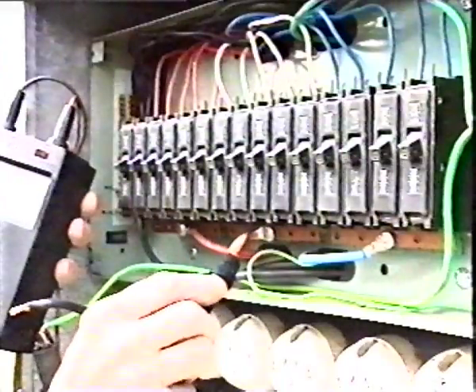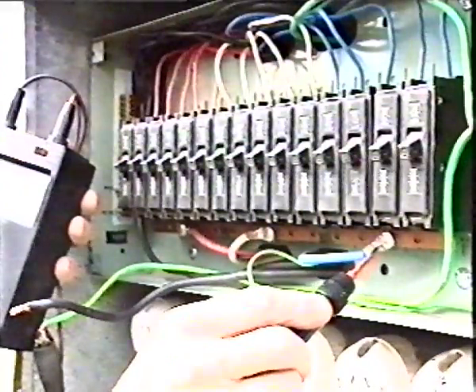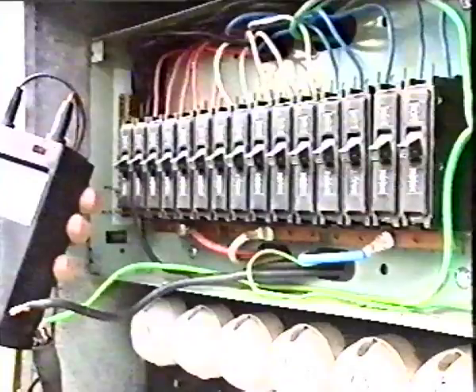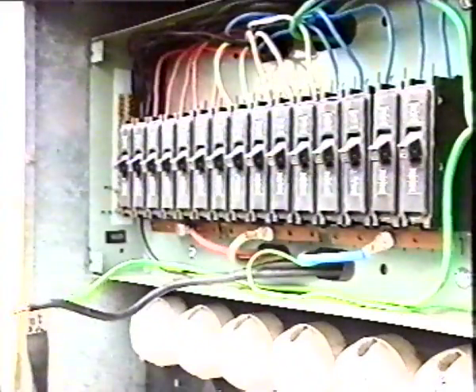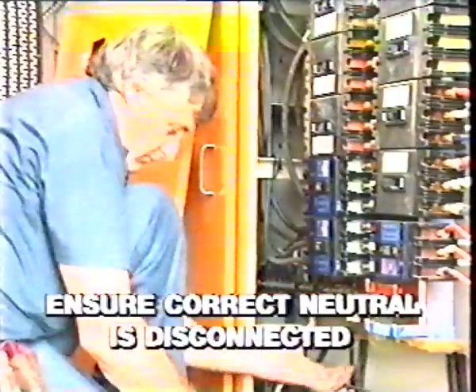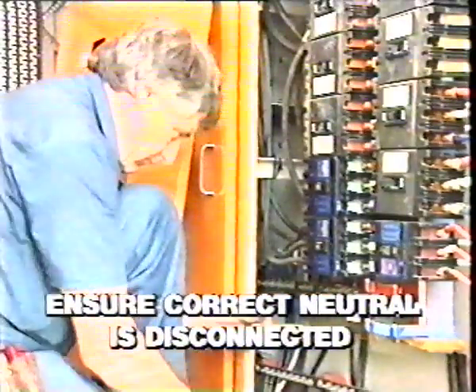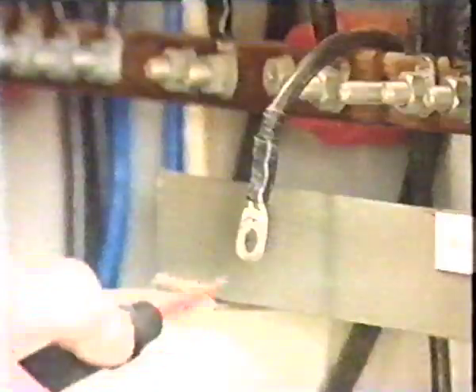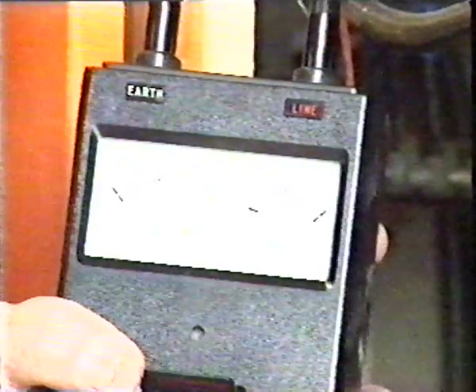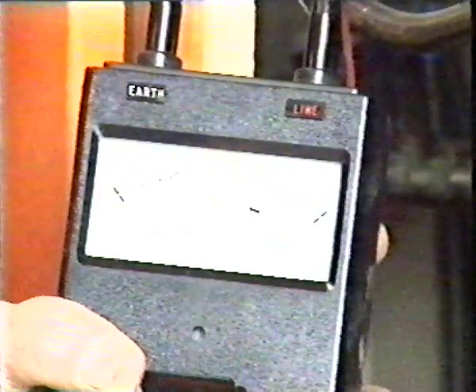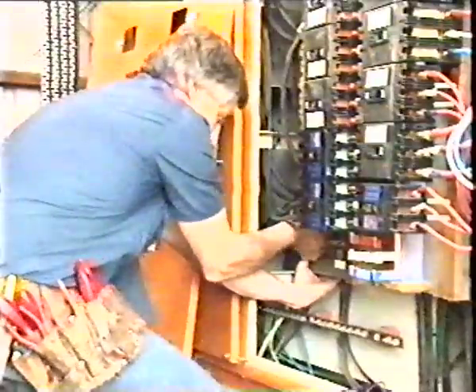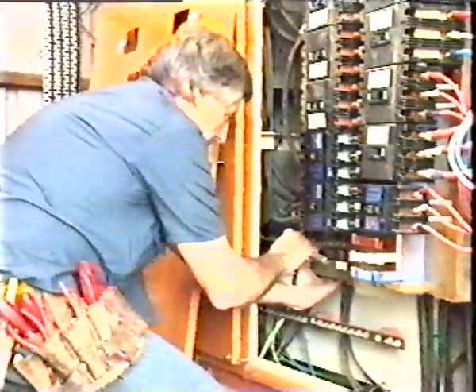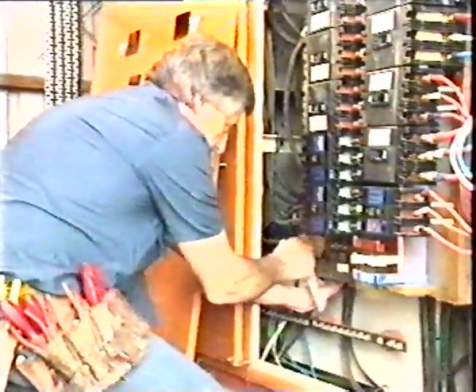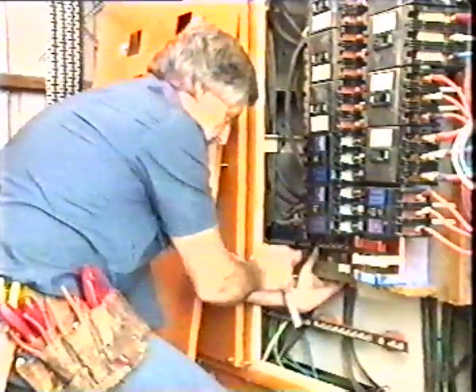Test the insulation resistance of the sub-main active conductors. A high resistance will establish that the conductor is not connected to earth and is therefore not a neutral conductor. Disconnect the sub-main neutral conductor from the supply switchboard neutral link. Test the insulation resistance of the conductor. Reconnect the sub-main neutral conductor to the neutral link at the supply switchboard and distribution board. Reconnect the main earthing conductor to the distribution board neutral link.